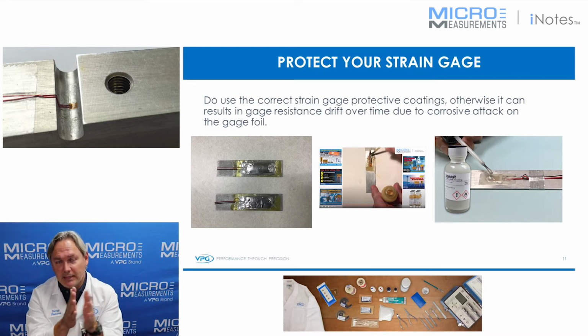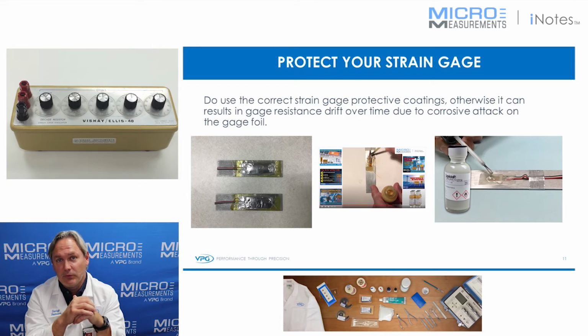And the problem with that is now you've got an electrically sensitive grid that's in that environment, and sometimes the inconsistencies or the chemical components that make up these compounds can provide an electrical path that could be a path to ground, or it could be some type of contaminant that could start attacking the grid of the strain gauge, in particular if you've got a voltage applied to it. So you do want to watch that, and if you're going to use an environmental coating that has not been qualified for strain gauge use, it's really up to you to do that.